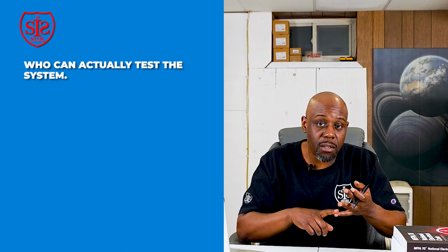They definitely focus on signal type: alarm, supervisory, trouble, monitor, and who could actually test the system, who's qualified to test the system. This is all what NICET is going to ask you on the Level 1 exam. So you need to be familiar with all of these particular categories and understand which direction they are sending you to answer that question correctly. All right, so I hope you understand the difference between testing and inspecting. We know that inspecting a fire alarm system is a visual thing. I'm looking to make sure everything is set right. And testing, I'm actually seeing if the fire alarm system is functioning the way it was designed.